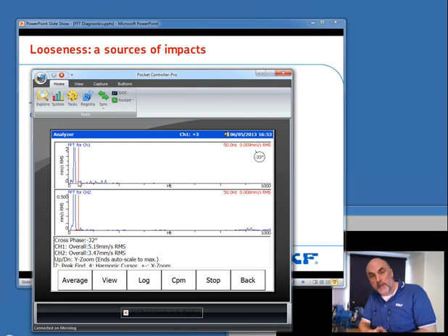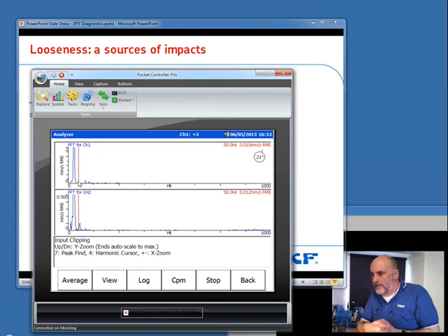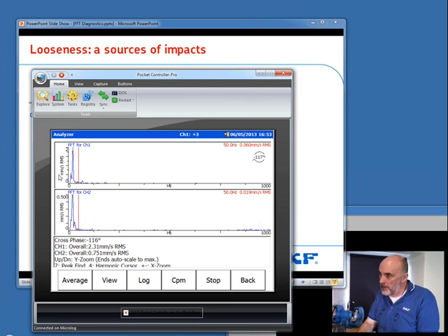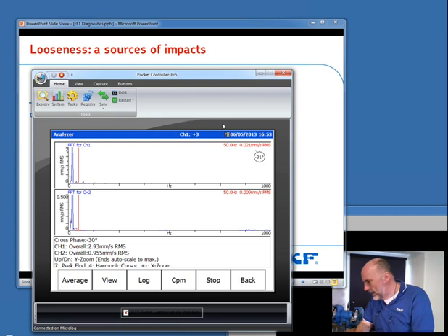Electrical problems, if you switch off the power, they disappear instantaneously the instant you switch off, and so it goes. It's just really a case of getting out there with your FFT analyzer, looking at the machine, and trying to harvest as much evidence as you can, concentrating on the shape of the spectrum and the phase, but that's not a panacea.